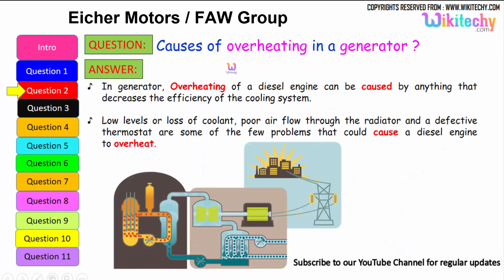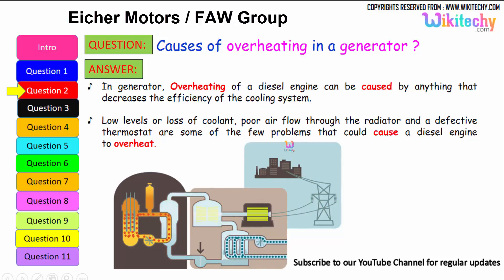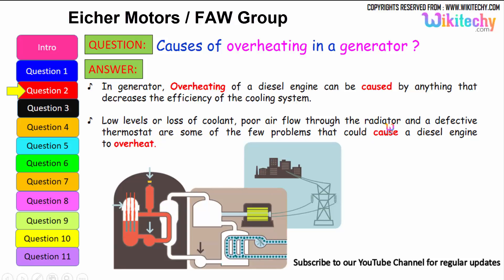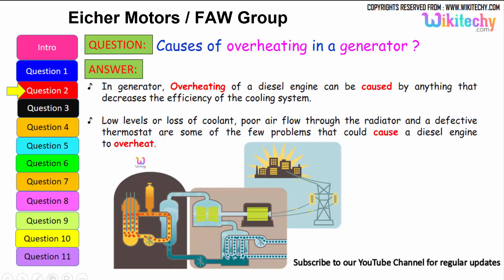Let's move on to the next question: causes of overheating in a generator. Overheating of a diesel engine can be caused by anything that decreases the efficiency of the cooling system. It can be due to the loss of coolant, low levels of coolant, poor air flow through the radiators, and a defective thermostat — which are some of the problems that could cause a diesel engine or a generator to overheat.